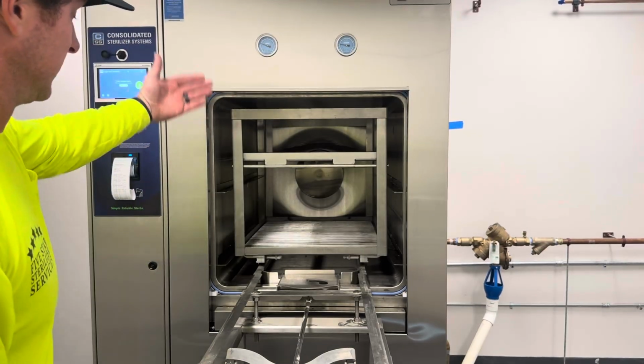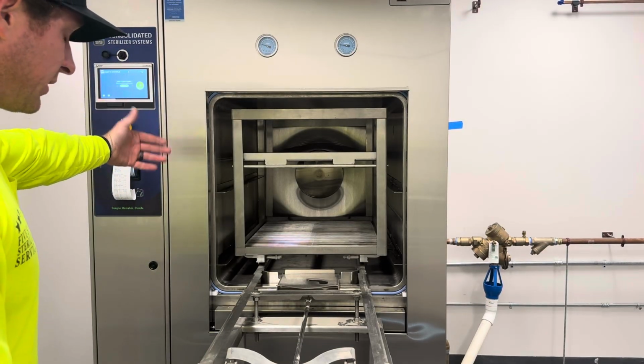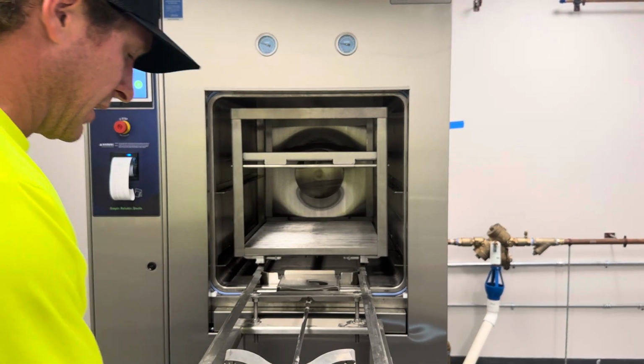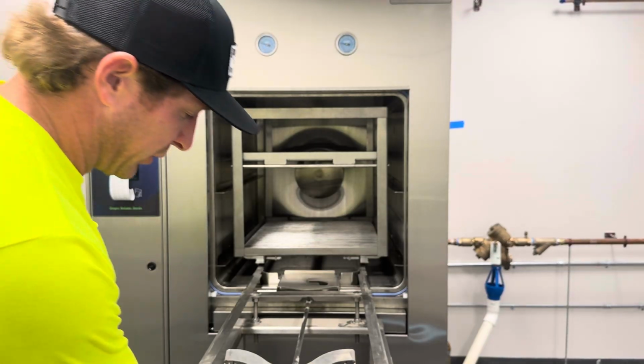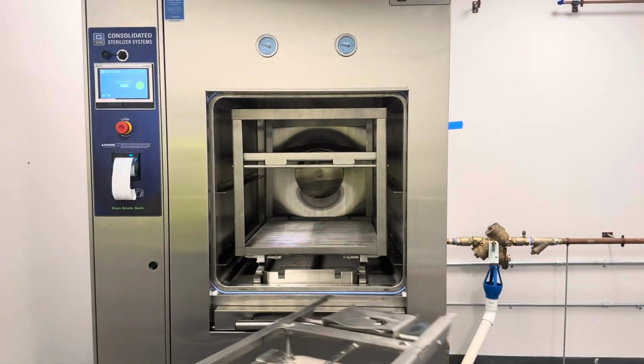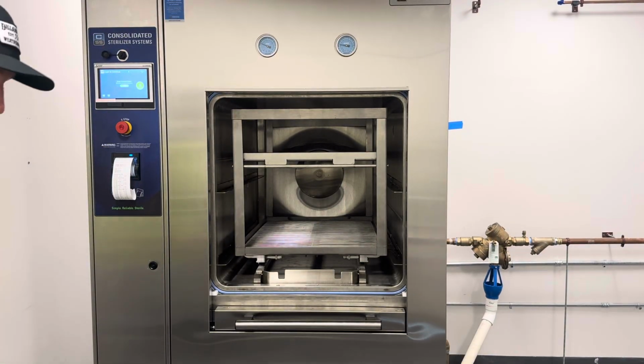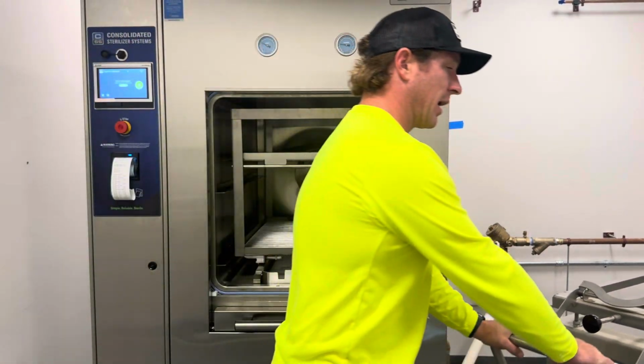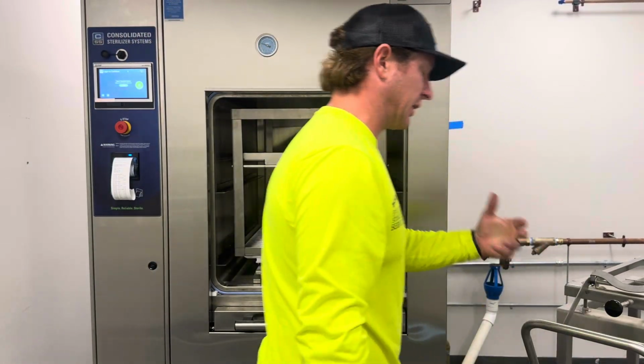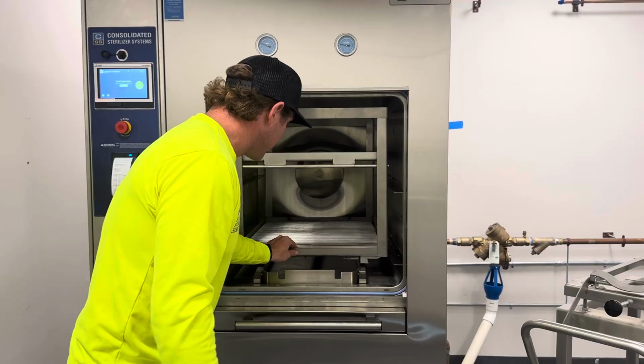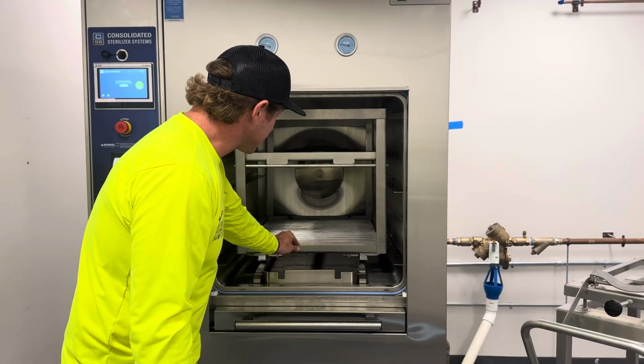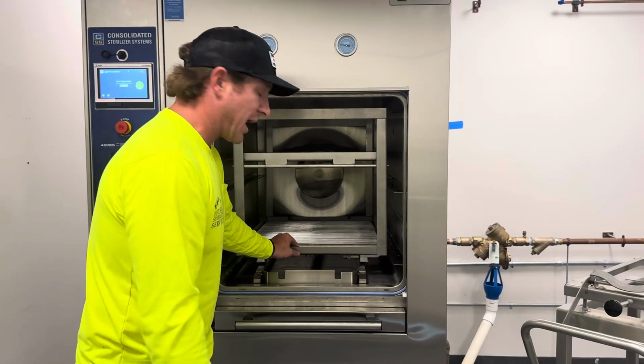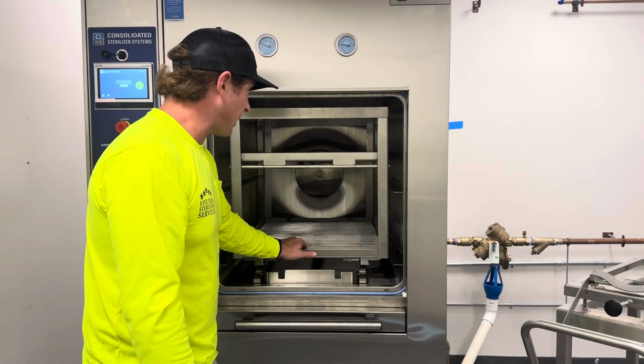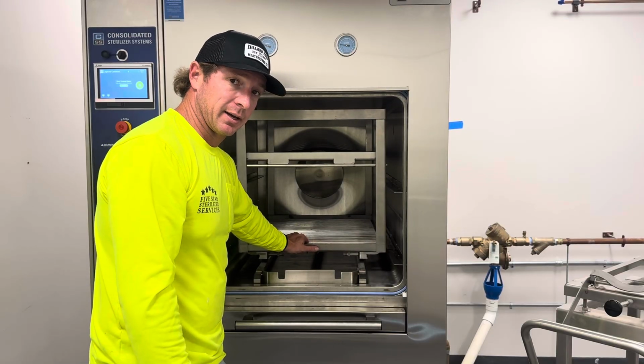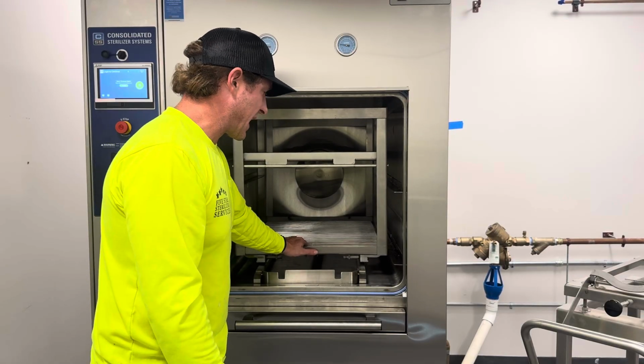Okay, now our transfer cart's in the chamber. We need to release the carriage. You would use this black button. You push it in, and that allows you to take the carriage away from the autoclave. And just the reverse for unloading. There is a little bit of play on this cart and carriage. I would recommend not to push it all the way back. Just find a happy medium right there.